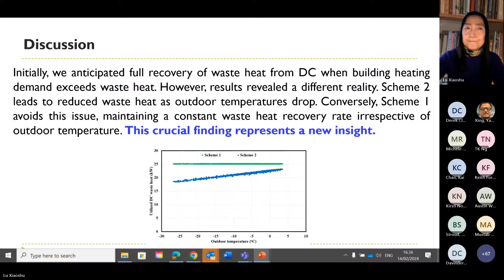For direct-to-chip cooling system and low-temperature space heating, our developed methods, scheme 1 and scheme 2, both can achieve very good results. One is 100% and the other is 83% recovery, corresponding to 71% and 63% annual recovery.